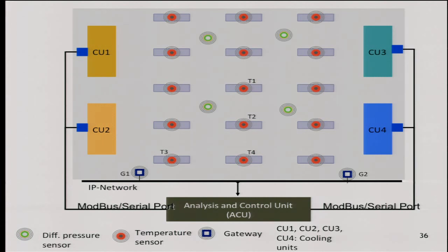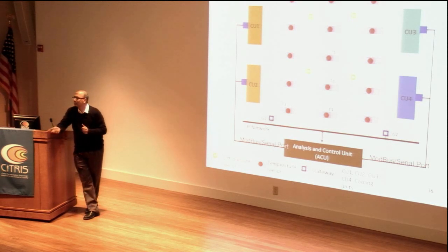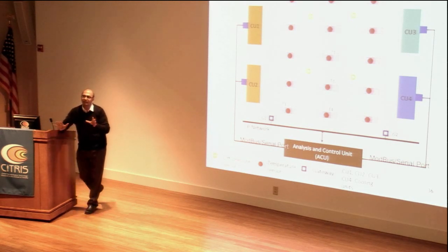So we try to understand 2 things. One, we try to understand that A affects B, and I can do that by changing how a certain CRAC changes and how it affects the behavior of that particular point or sensing point. And that's why you need to normalize the data center. That's why you need to manually optimize it. That's why it makes sense to do that before you go and do the control. So the first point, that A affects B, I need to know. And the second thing I need to know is how much I change A that will affect the change in B itself.